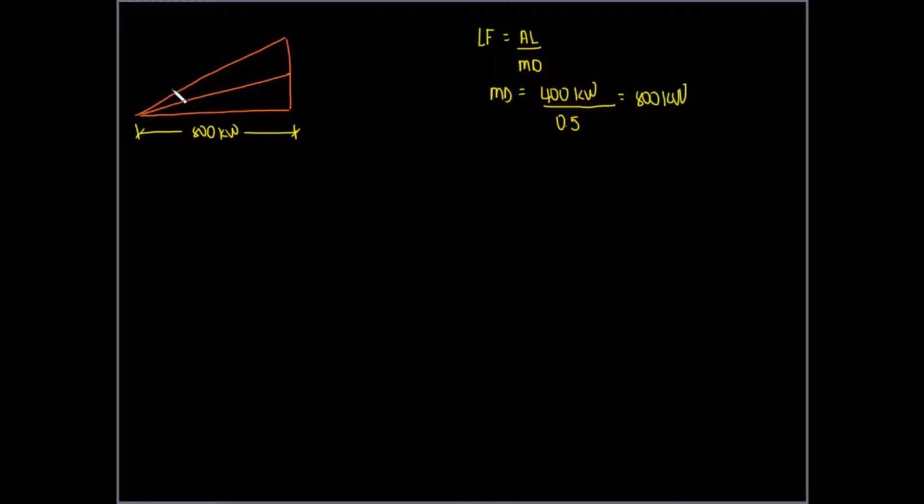Now, this is your power angle using the original power factor, which is 0.8. So inverse cosine of 0.8 must be 36.87. So this is 36.87 right here. And then it's now corrected to a new power factor, which is 0.95. So this will be inverse cosine of 0.95, which is 18.1949.